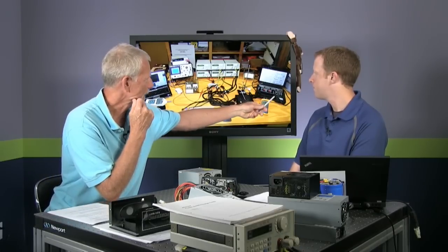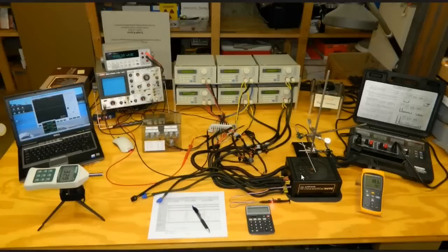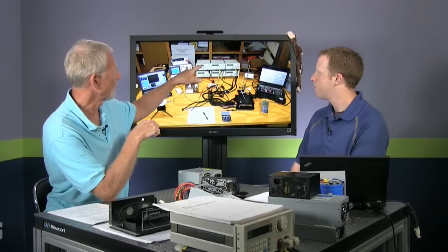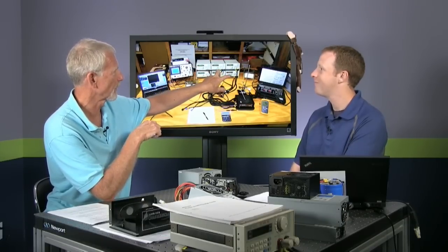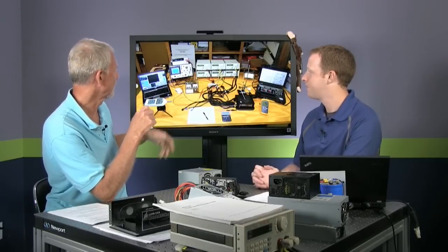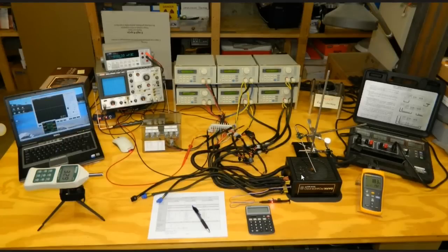The Extech power analyzer monitors all the AC power going into the power supply. I've got a Fluke temperature meter with thermocouples on the inlet and outlet. There's a bank of six DC programmable loads in the back—3.3, 5 volt, and four 12 volt sections. I've also got additional 12 volt loads if needed, so I can load test bigger power supplies up to 1,500 watts, plus a bank of precision resistors for the -12 and +5 volt standby loads.